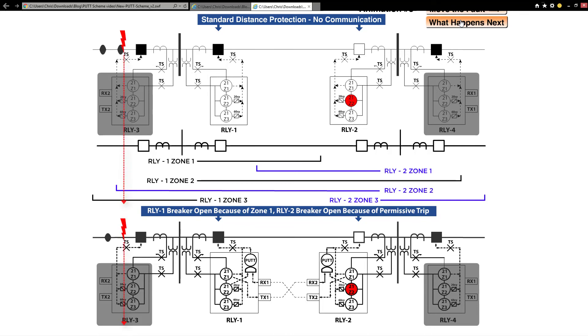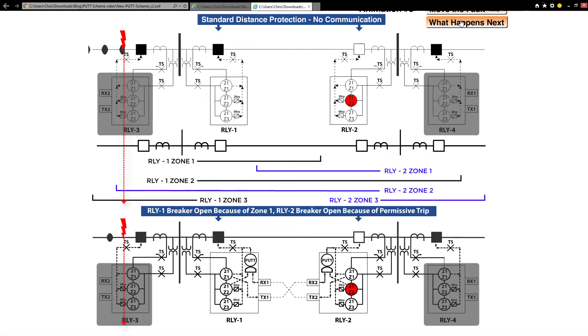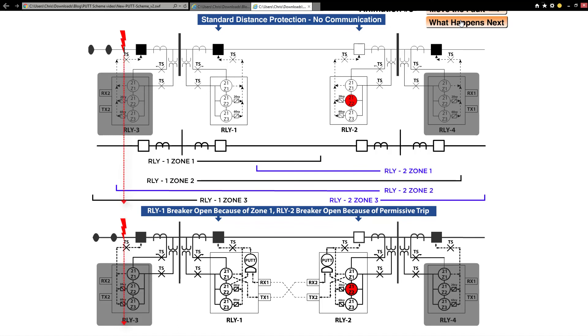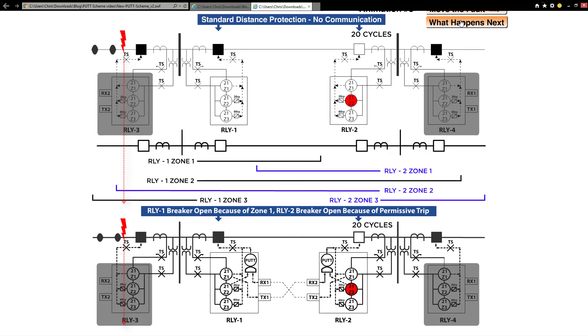That's the dirty little secret of communication-assisted trip schemes — they are only installed to trip faster if the fault occurs beyond Zone 1 to the end of the line. All of this time, money, effort, and extra testing technology only saves us 20-40 cycles inside a very narrow window. Why do we do it? The primary reason is system stability. Studies of the power system show a relationship between fault duration and system stability — that extra 20 cycles of fault current could cause a much larger outage, so we want the fault cleared as soon as possible.